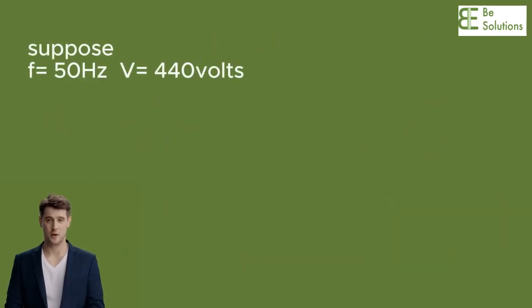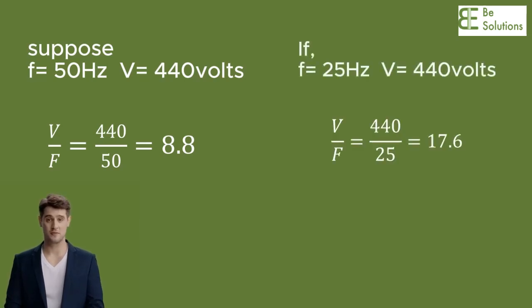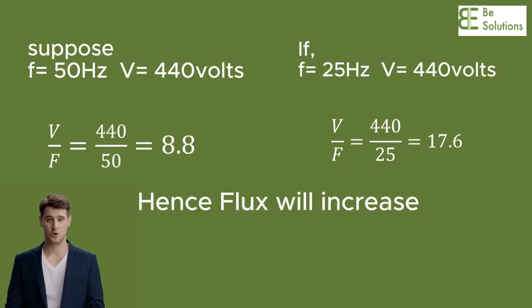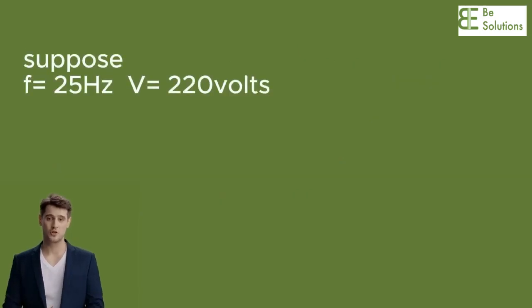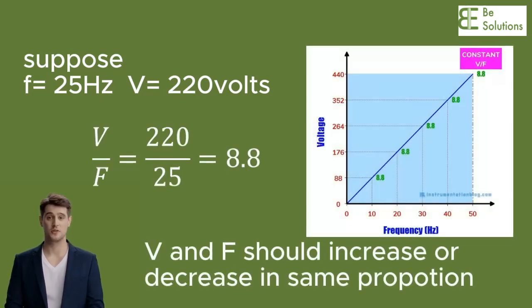Let's understand this phenomenon with the help of an example. Suppose we have a motor running at 440 volts, 50 Hz frequency. Now suppose we decrease the frequency to half, so F equals 25 Hz, and voltage remains constant. Here V/F increased, which will increase the flux, so the core will not carry that flux and will cause excessive heating. So, with the decrease in frequency, the voltage should also decrease in the same proportion. In the above case, voltage will decrease to 220 volts. Hence the flux will not increase.